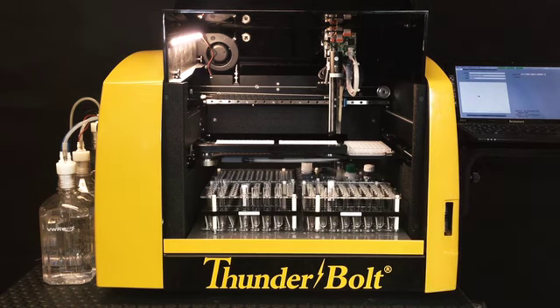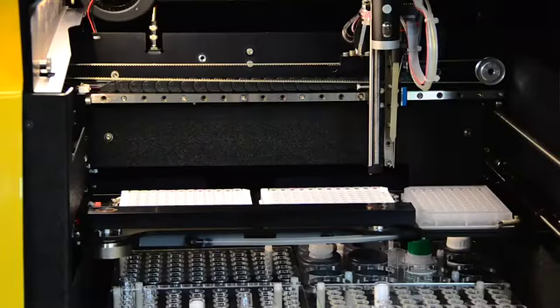The other thing, the main one to me, is the probe. Our probe can pick up 1 microliter, and because of that, we can perform 1 to 100 dilutions directly into the well. Many tests, including most infectious disease tests, involve a 1 to 100 sample dilution. Those samples can be diluted directly into the wells, and the timing starts the second the sample and diluent hits the well. Therefore, we skip past the whole start of most tests, which includes an instrument picking up diluent, dropping off diluent, picking up sample, dropping off the sample into the diluent, mixing the diluent in the sample, then transferring the diluted sample to the plate.